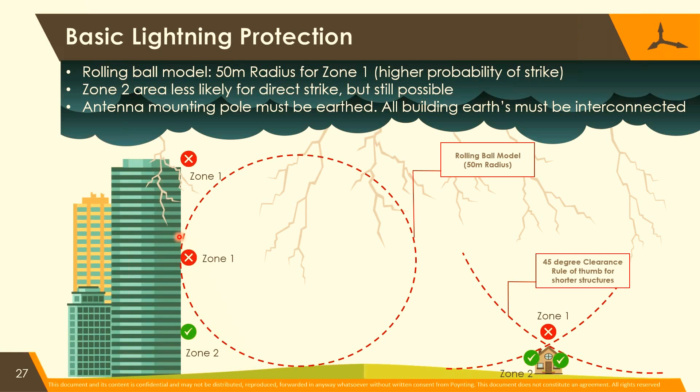So if you look at this rolling ball, if it rolls up, lightning can hit anywhere on this building, even though this is higher. People didn't believe me — we've had high-rise buildings where someone on the fourth floor gets hit by lightning. This is a very real impact once a building is more than about 50 to 60 meters high.